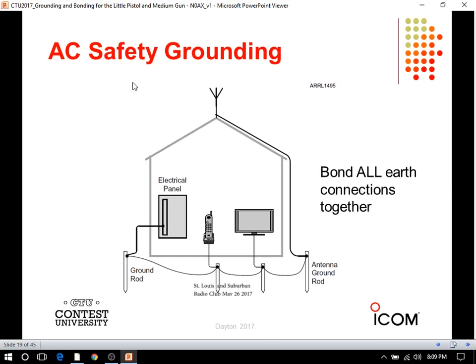You want to bond all of your ground systems together. The cable guy will come out and run your cable and put in a little ground rod. The telephone guy will come install your service box and put in a little ground rod. The electrician will come out and put in a ground rod. Then you've got your antennas and you put in another ground rod. Well, they've all got to be tied together using number 6 AWG and the right kind of clamps, and bury that wire. So you're creating a protective ring around your house. If you can get everything to come to the same point, use the same ground rods - that's optimum, but it's not always possible. Your shack seems to always be on the other side of the house from the circuit breaker box, so you've got to run a ground wire all the way back. But bond everything together - that's a must.